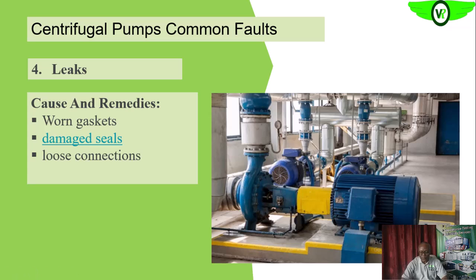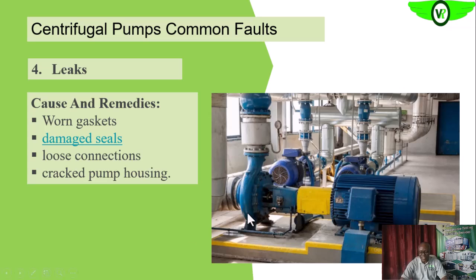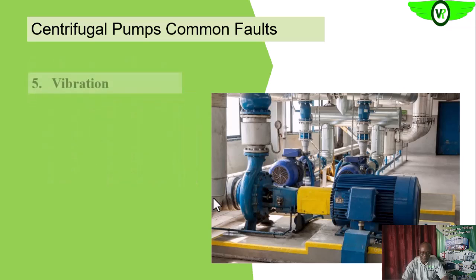Loose connections at flange joints — any loose bolts — can cause leakage that affects the flow rate and the amount of fluid delivered to the process. A cracked pump housing is also a cause: since the fluid pressure is elevated inside, it will leak out of cracked points. If there is a crack, it can be sealed temporarily until the pump can be replaced or a replacement installed. Those are the main causes of leaks in a centrifugal pumping system.